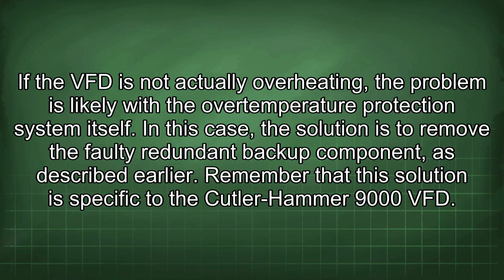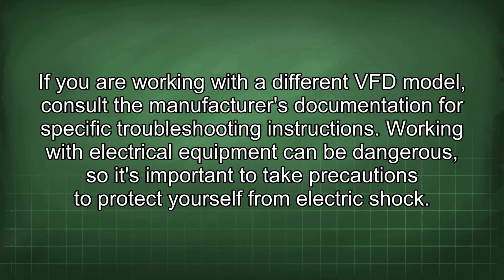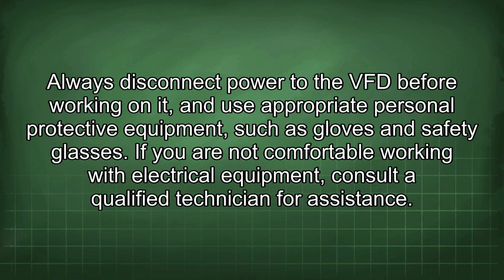Remember that this solution is specific to the Cutler-Hammer 9000 VFD. If you are working with a different VFD model, consult the manufacturer's documentation for specific troubleshooting instructions. Working with electrical equipment can be dangerous, so it's important to take precautions to protect yourself from electric shock. Always disconnect power to the VFD before working on it and use appropriate personal protective equipment such as gloves and safety glasses. If you are not comfortable working with electrical equipment, consult a qualified technician for assistance.